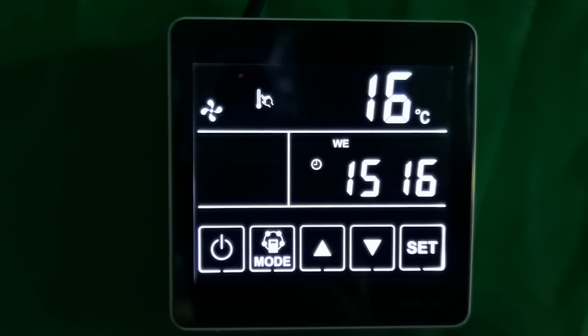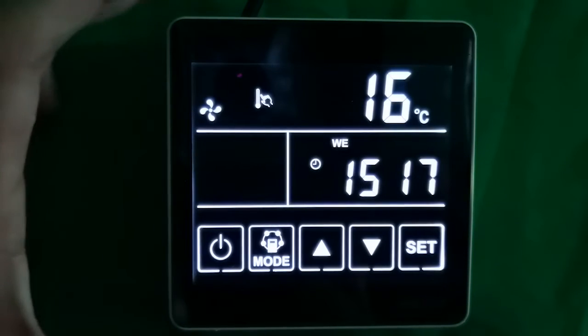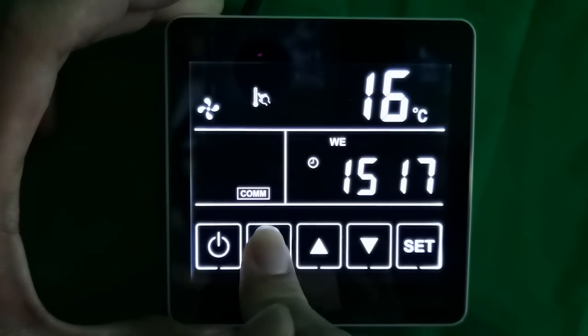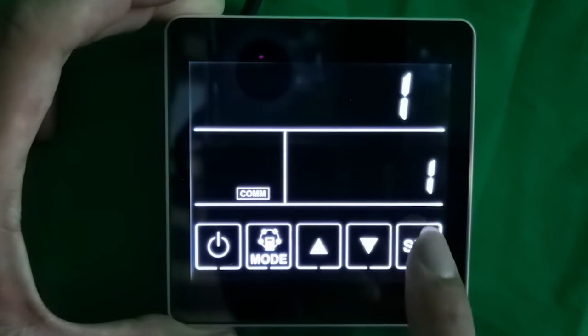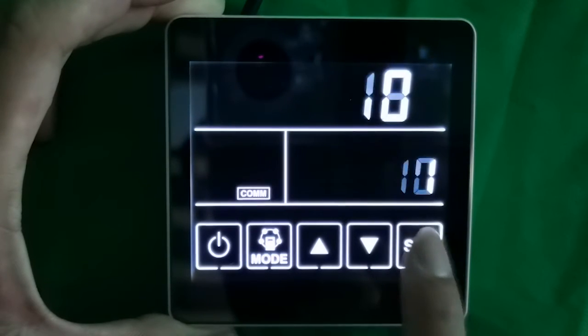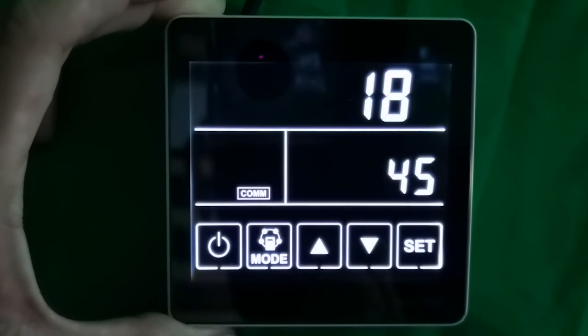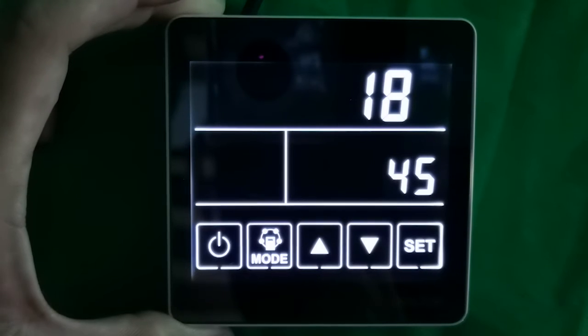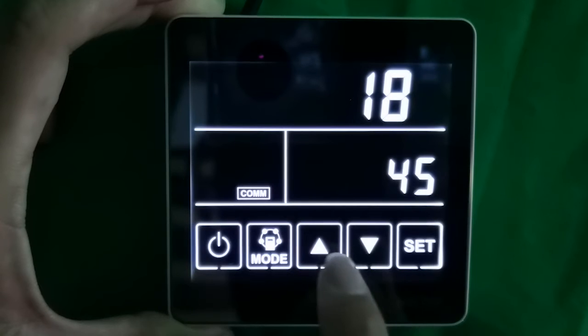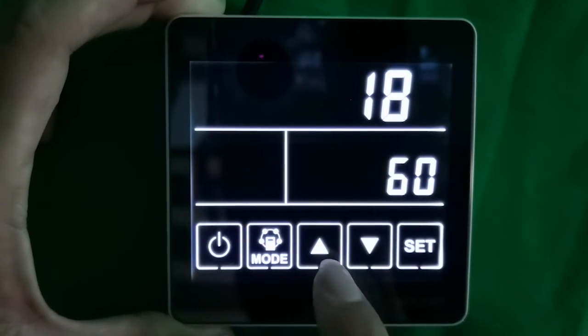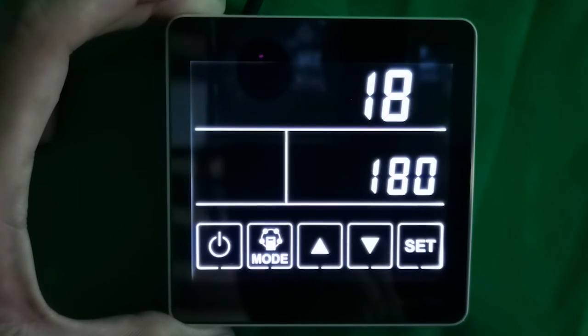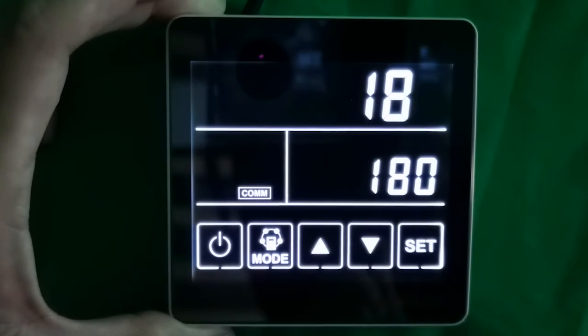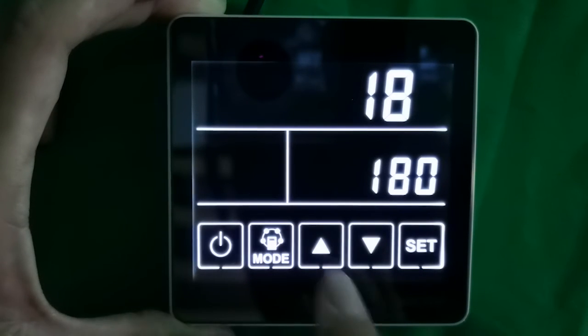Let's go to parameter 18 for the filter alarm setting. Long press the mode button, then press set through parameters 2, 3, and up to parameter 18. We have four parameter values available: 45, 60, 90, and 180 days. If I want to set the filter alarm every 90 days, I set parameter 18 to the value 90 days.